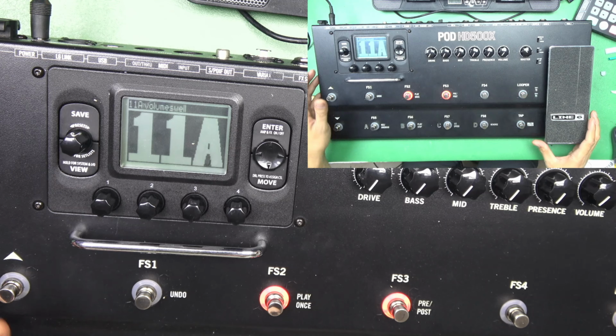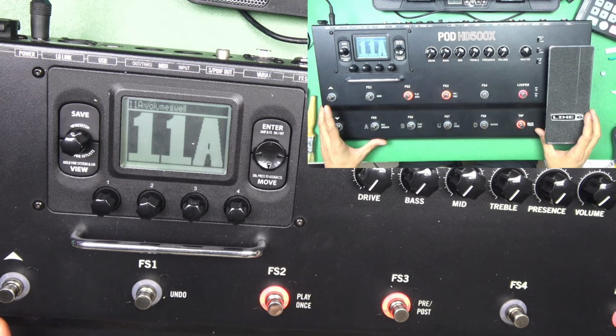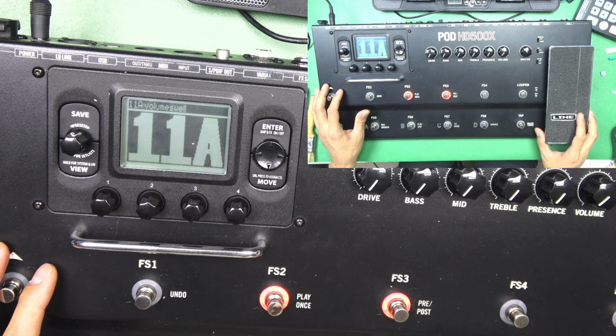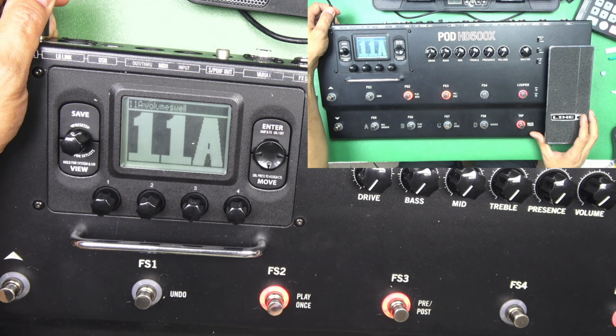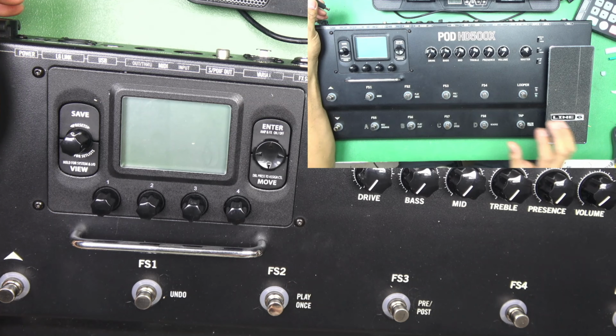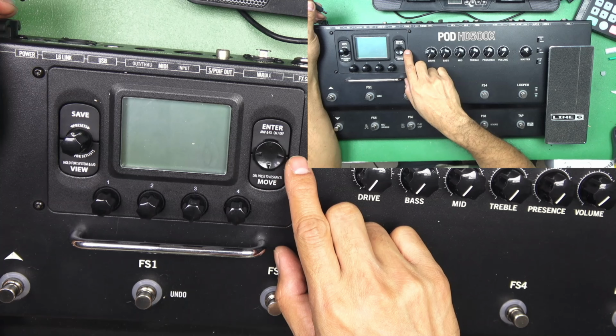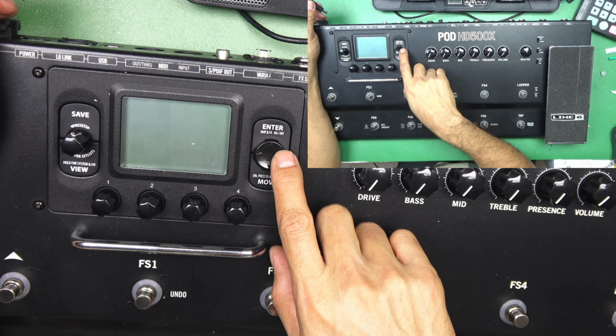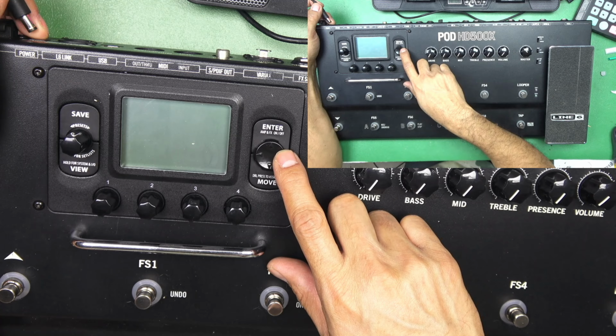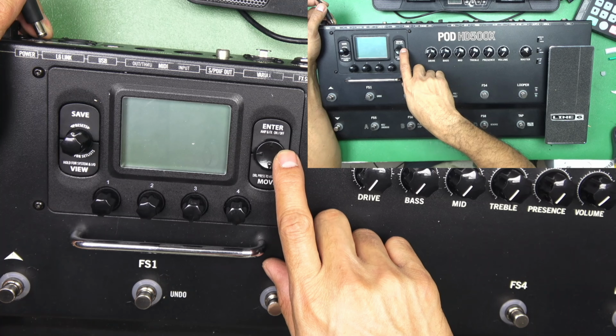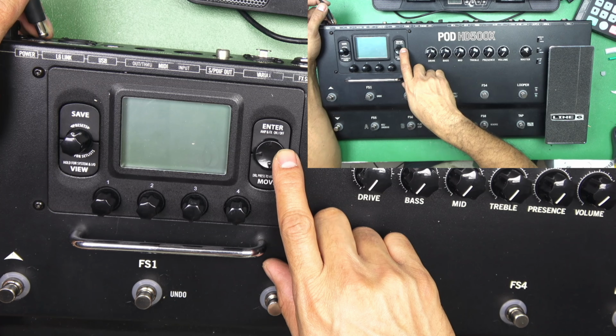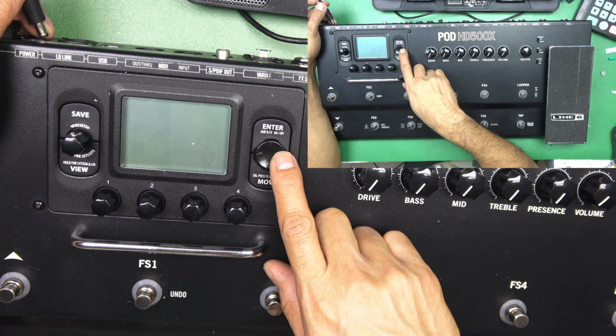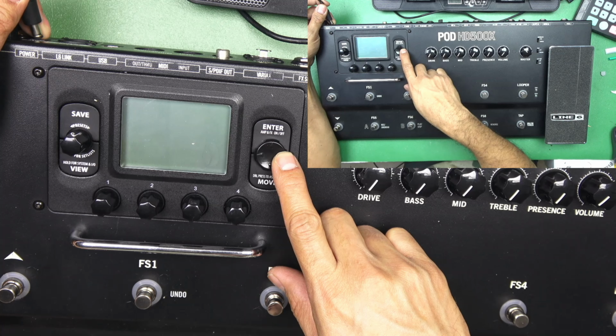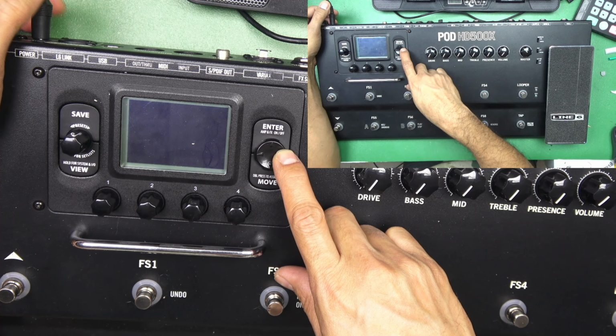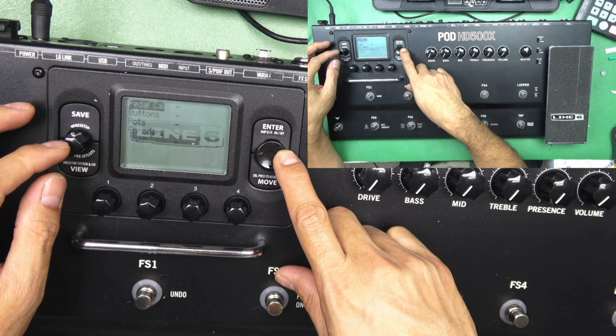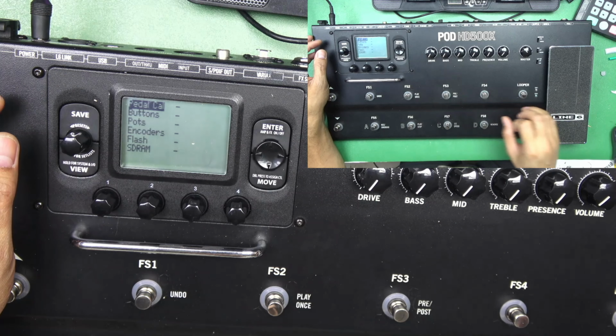Here I am going to perform a pedal calibration on POD HD500X. First step, you have to disconnect the power supply and press the right arrow button, press and hold. While pressing this arrow key, the button on the right side, you have to reconnect the power supply. Hold it down until you see the display and release.